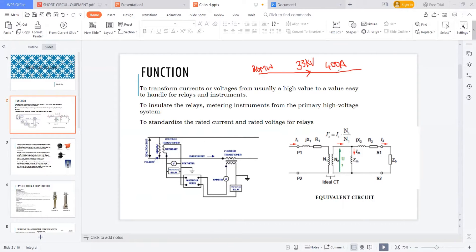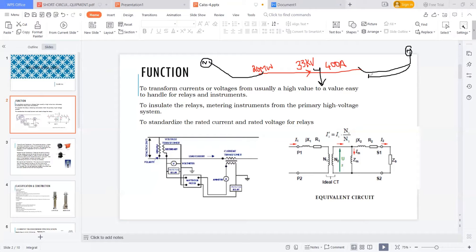Now, if a fault occurs in my system — suppose a fault occurs in this feeder — obviously the generators on both sides of this feeder are contributing to the fault. This is an infinite grid, and all these generators are feeding the fault. The current flowing in this feeder will no longer be 400 amps; it will definitely be more than 400 amps.